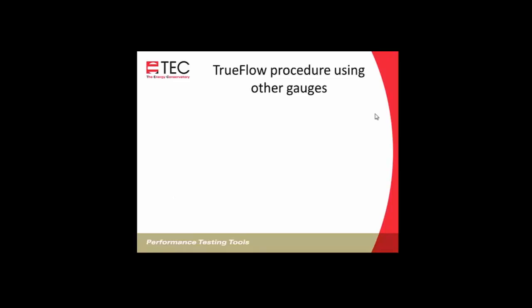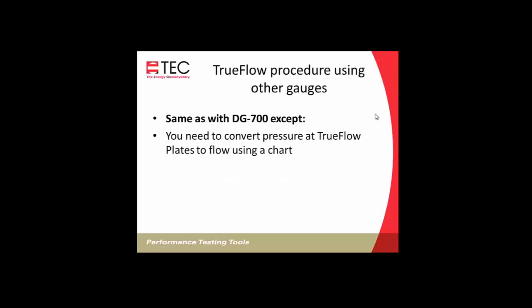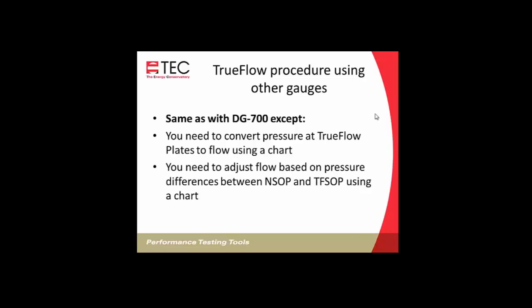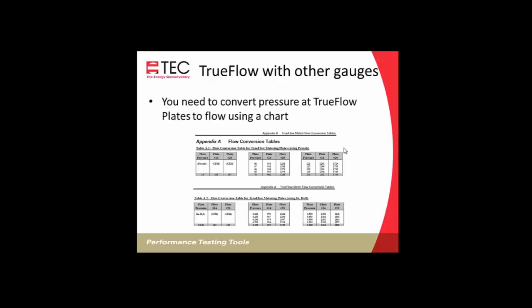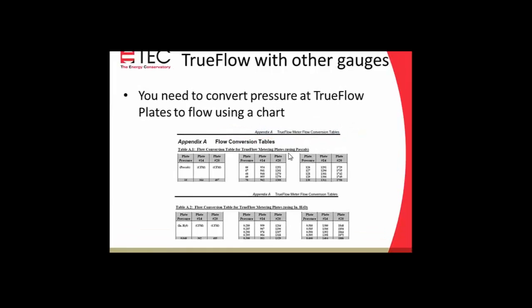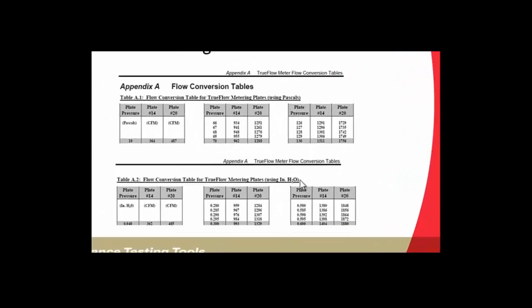Next, we'll talk about the TrueFlow procedure using other pressure gauges. And it's basically the same as with using the DG700, except you'll need to convert the pressure reading you get at the TrueFlow plate. So that's on channel B is where you'll have the TrueFlow plate. So you'll be reading a pressure from the two tubings from the TrueFlow, and you use that on a chart to convert pressure to flow. And then you'll also need to adjust the flow based on the pressure difference between the normal system operating pressure and the TrueFlow system operating pressure using a chart or a formula. So to use the charts, what I'm showing here is Appendix A of the TrueFlow manual, and it has 2 different charts, one using pascals and one using inches of water.